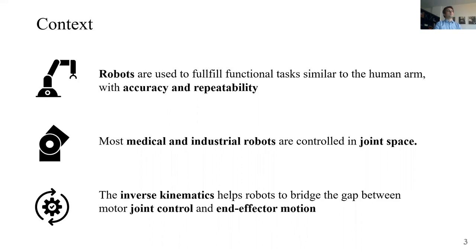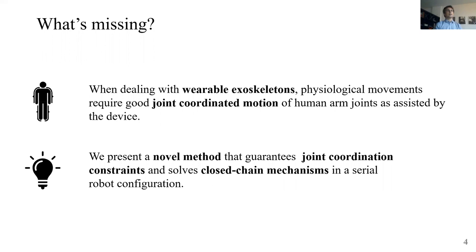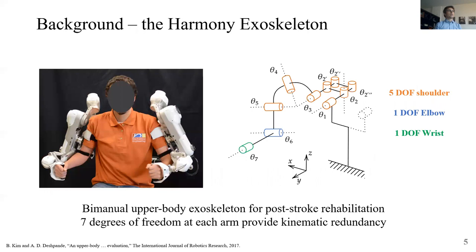So what's missing? In the case of wearable exoskeleton it is not important to precisely control the position of the end effector. It is more important to provide a good coordination among the joints of the human arm. This is why we present an inverse kinematics algorithm that exploits the redundancy of the robot to solve for conflicting multi-constraints. Some of these constraints can derive from the need of coordination among joints and some other can also derive from closed chain mechanisms that cannot be solved with traditional serial robot methods.